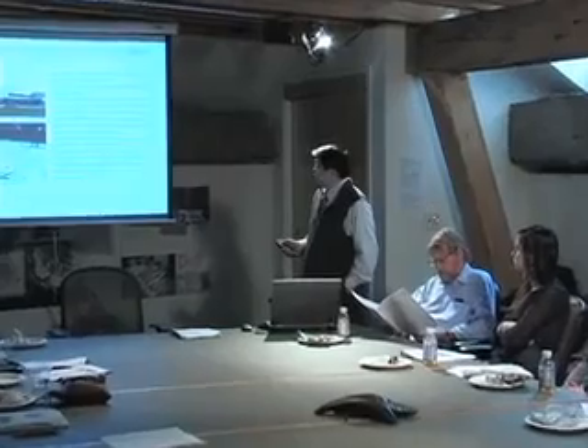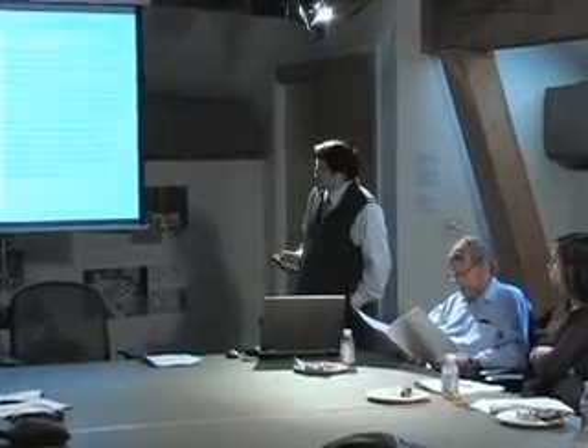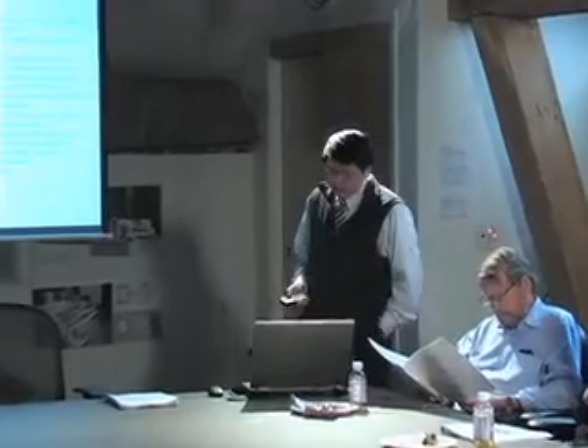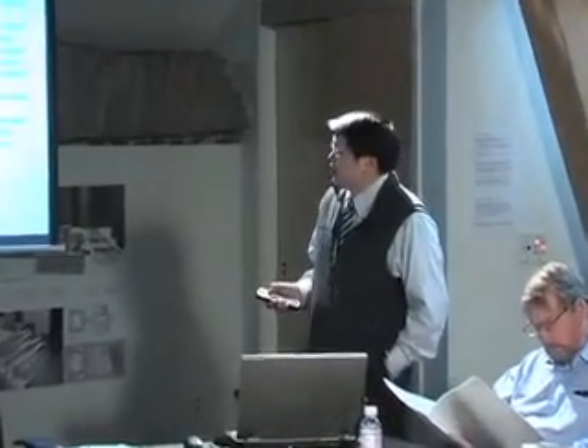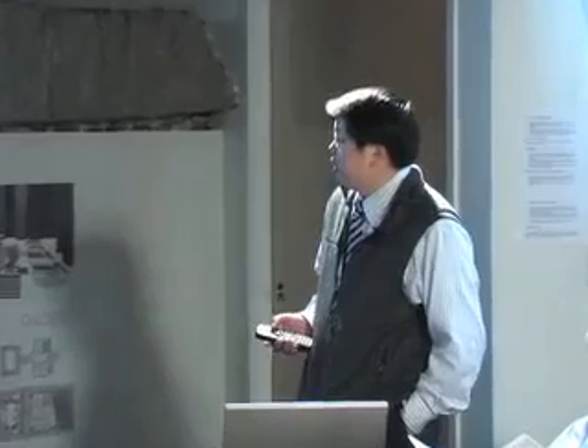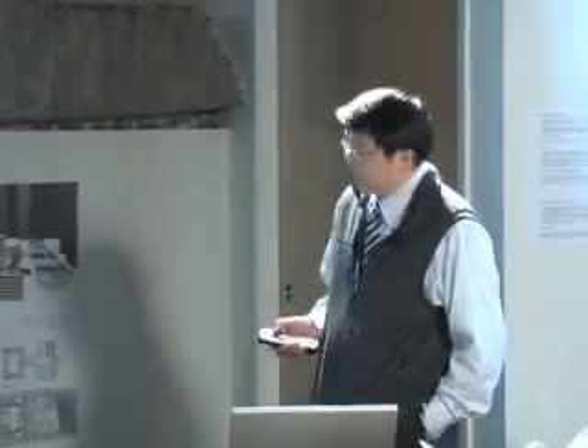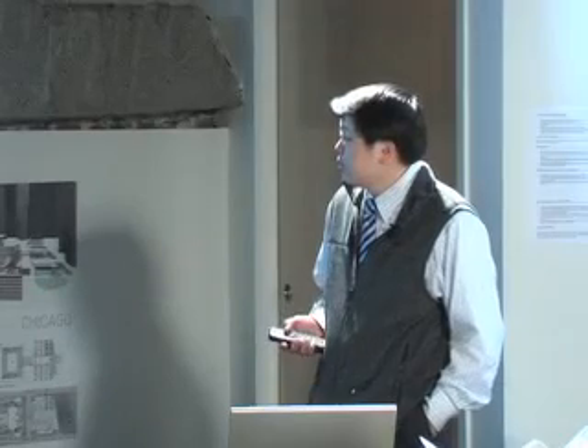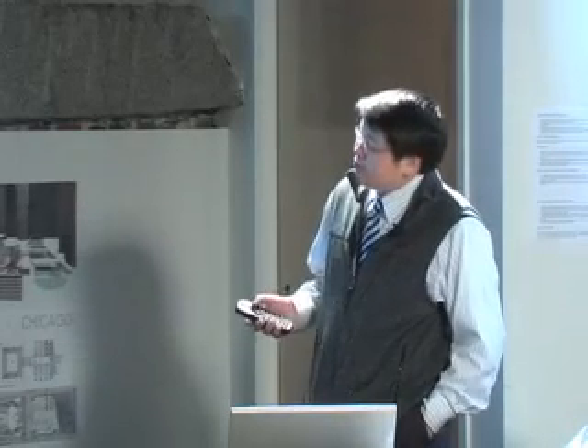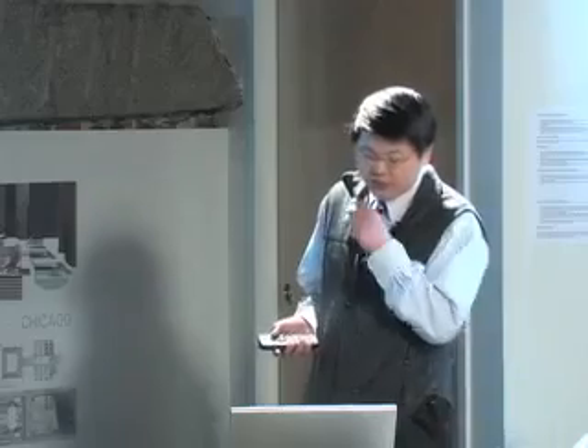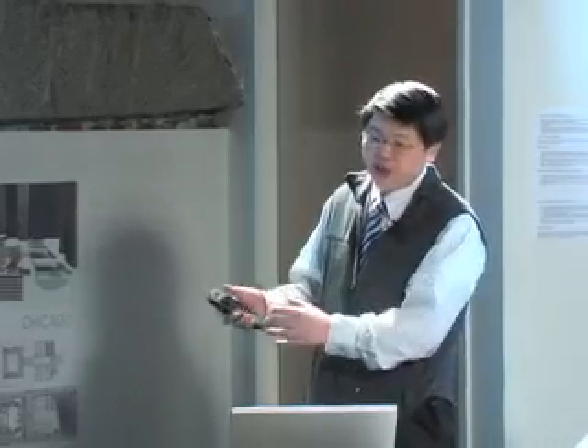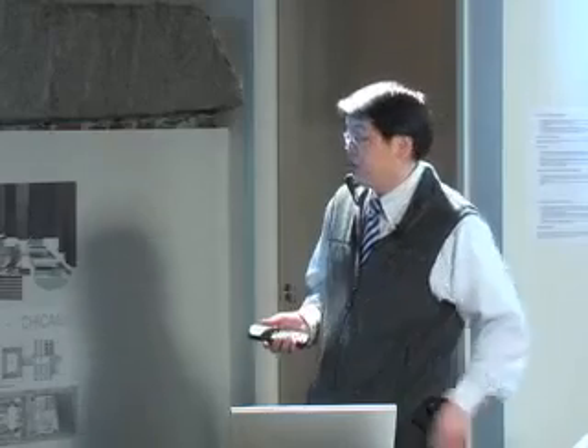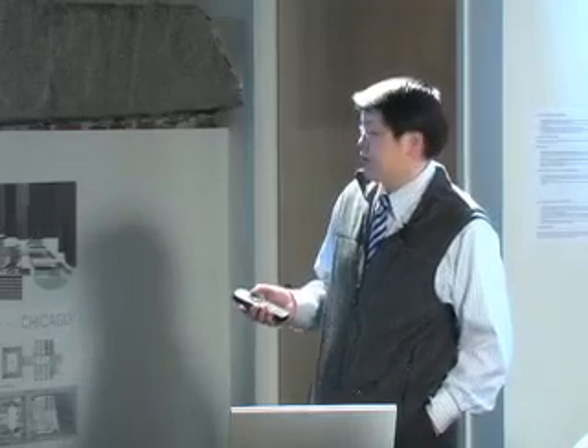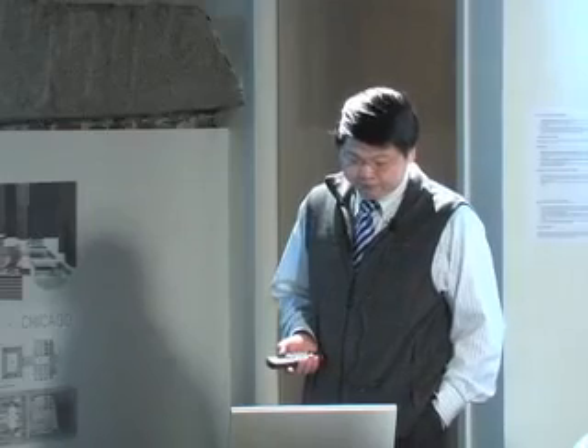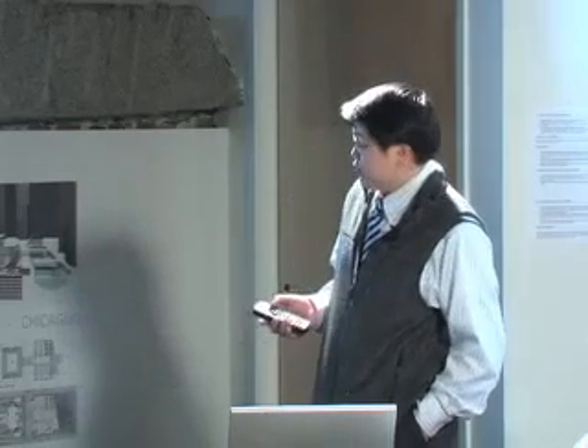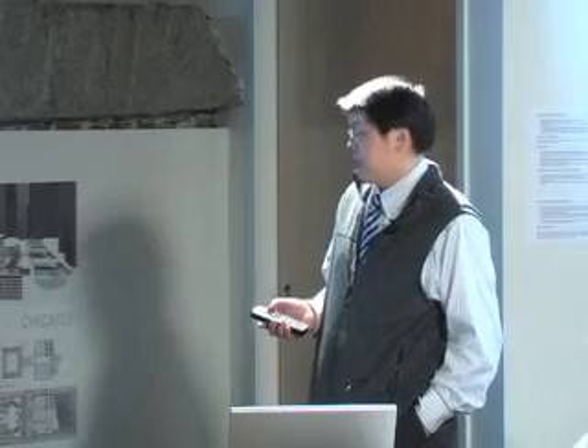They use water-to-air heat pumps for space heating and cooling. They also have water-to-water heat pumps to do cooling, to maintain the ice temperature. And the water-to-water heat pumps are also used for domestic hot water heating. And one reason why this is so efficient, as my previous slides showed, where you have multiple heat pumps, some do cooling and some do heating, you get the efficiency of diversity. The rejected heat gets utilized. They also used energy recovery wheels, and some other energy saving measures.